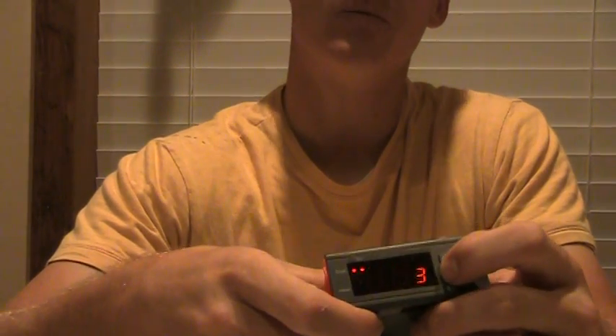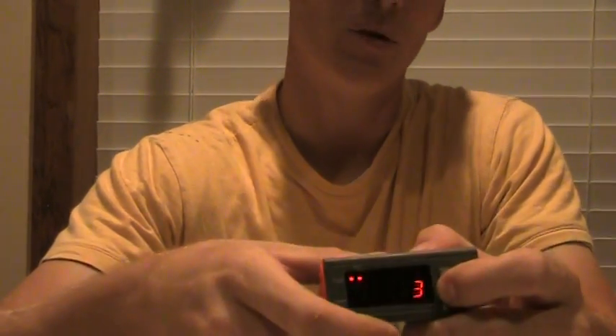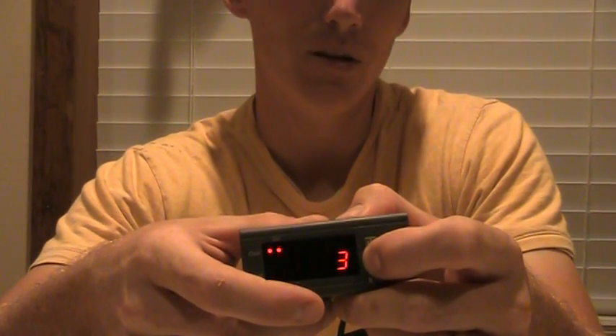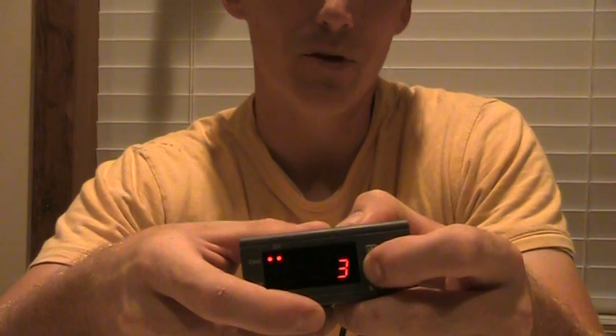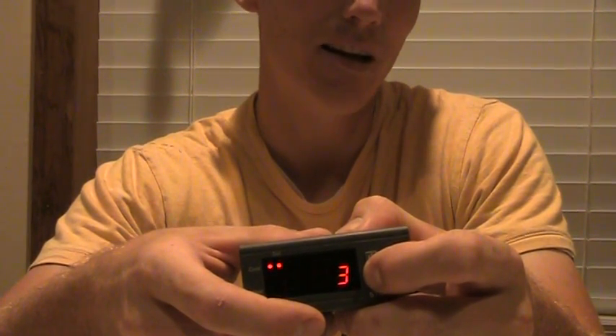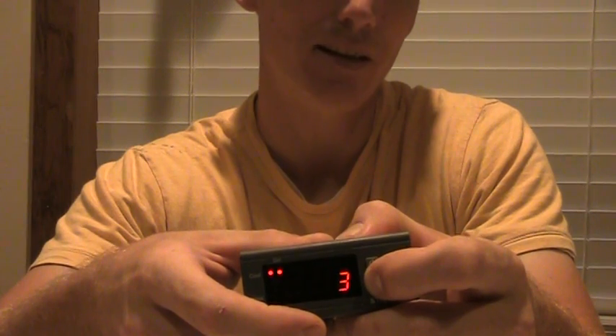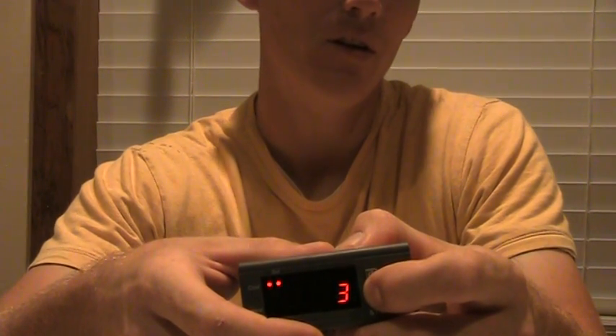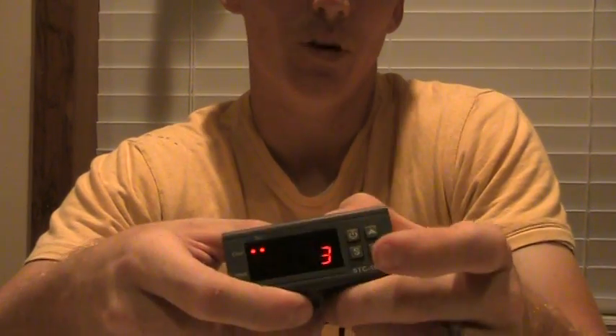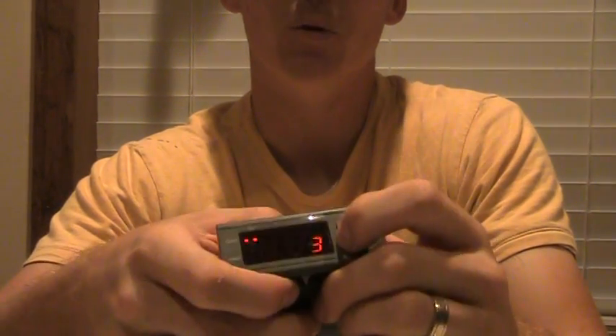If you hit the S again, you'll see it says three minutes. That's for compressor delay. If you had a chiller hooked up to it with a compressor for the cooling side, it only allows that item to come on three minutes after the last time it went off, so it doesn't come on too quickly and overheat the compressor. We're not going to be using that, so we'll just go past it.